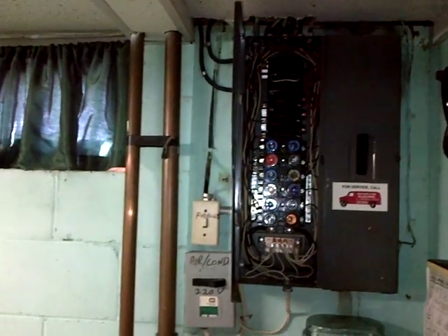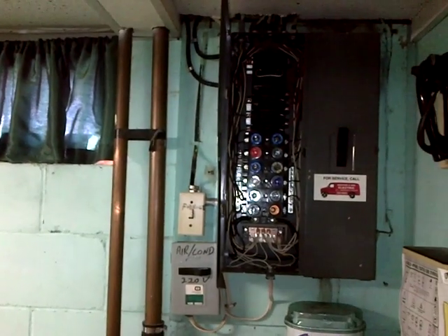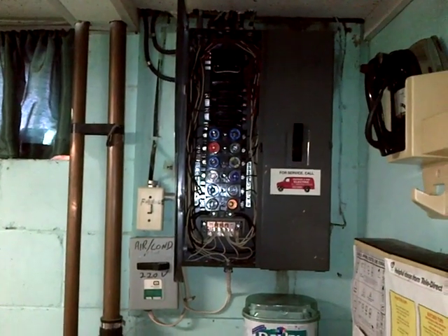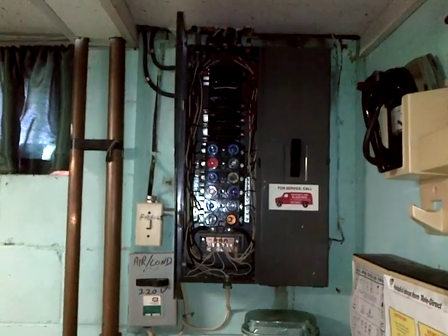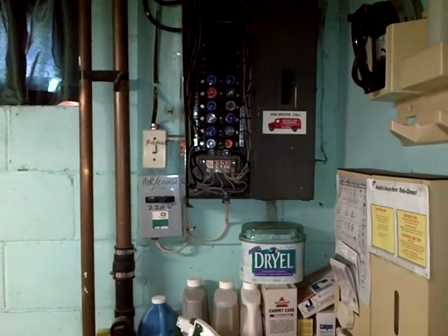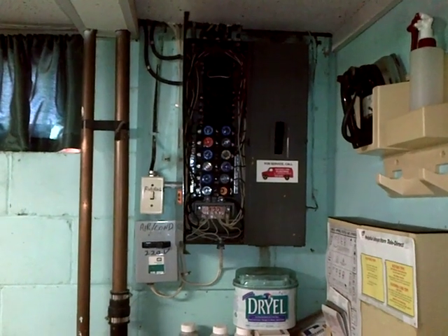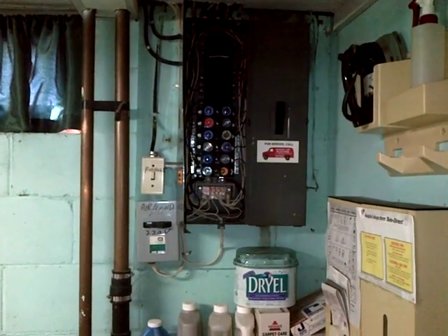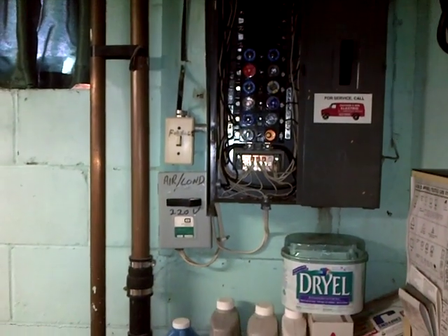We're a little bit tight to the left — these water pipes here, this copper. I'm not sure about fitting a panel horizontally, but certainly vertically it will go in, with an extension of a lot of these branch circuit sub-cables. I still have to make my decision — I'll take some measurements and see what's the best course of action. I don't see a stove; I see an electric dryer and an air conditioner.